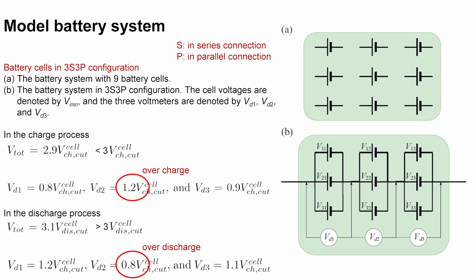In the discharge process, although the total voltage of the battery system is above the minimum total discharge voltage, V total larger than V total discharge cutoff, one or some battery cells might fall below the cell discharge cutoff voltage, in other words Vmn less than V cell discharge cutoff.